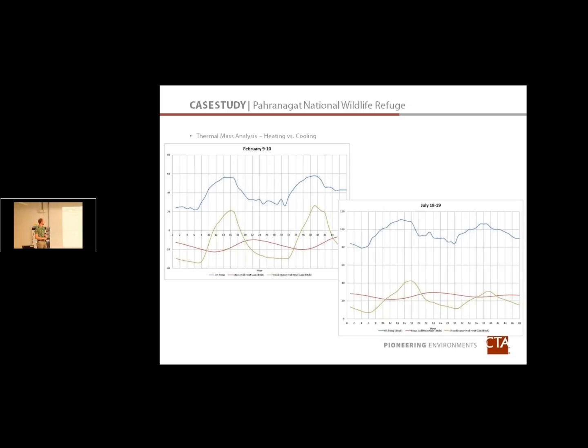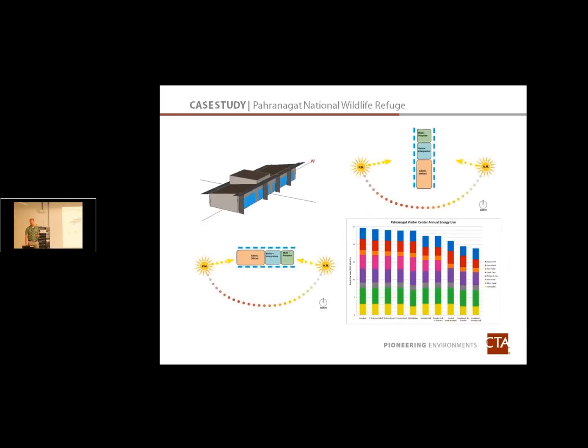On the heating side, the same is true. So the peak heating temperature happens at, what is that, 4 in the morning or 6 in the morning or something. And that load is now, so we're looking at most negative for your heating loads, and that's now transferred to 10 or 12 in the morning. So now our mechanical system's having to account for all that extra heat. In this case we found it almost to be a wash between a stick frame and the mass. And the mass is quite a bit more expensive, so we decided it's not worth the investment in this case. Let's go with just a stick frame building, fairly well insulated.